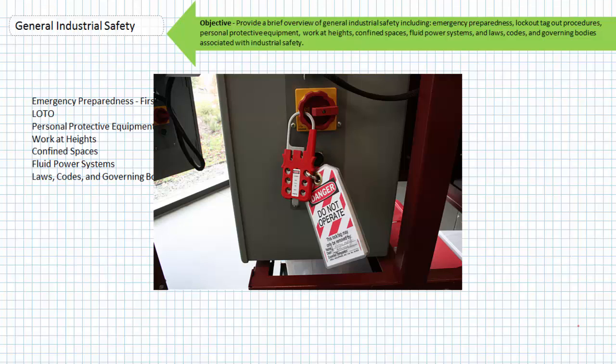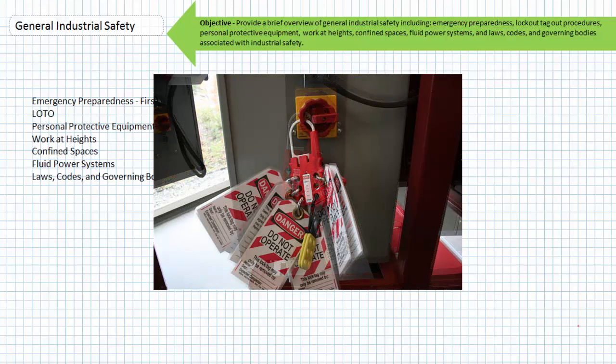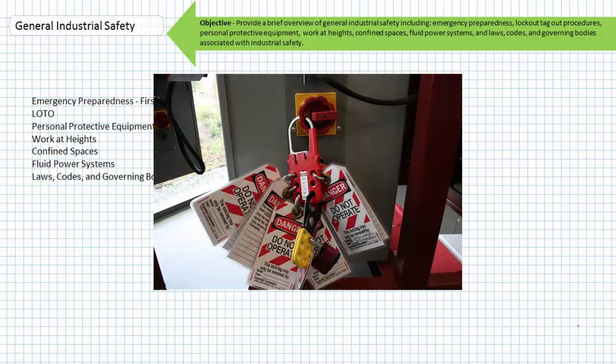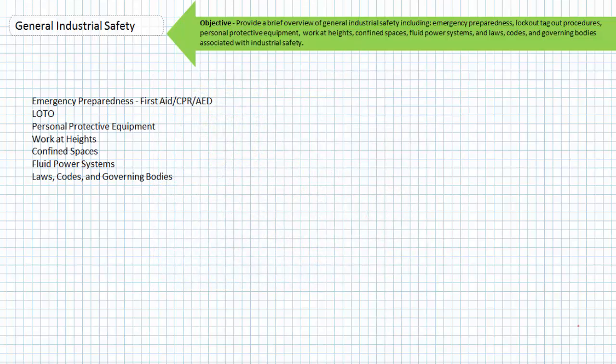Teams of workers will use the locking mechanism and a hasp with individual padlocks. Each worker has their own padlock and their own key. Achieving a state of zero energy means that there is no source of hazardous energy present, nor can any build up during the course of a maintenance procedure.